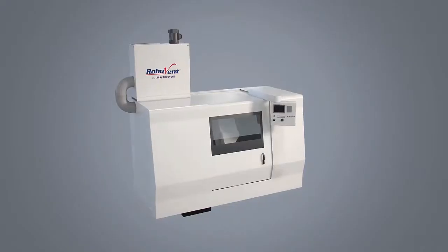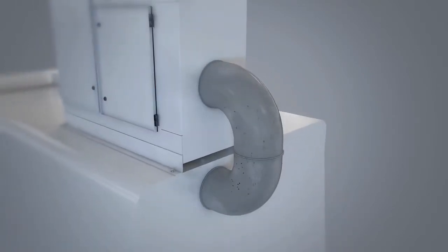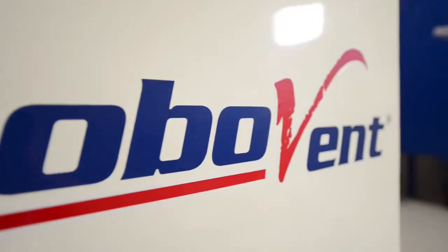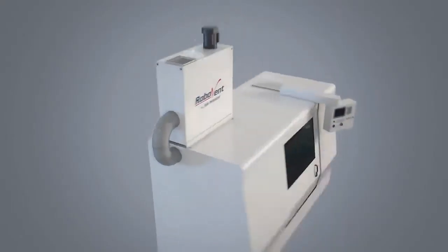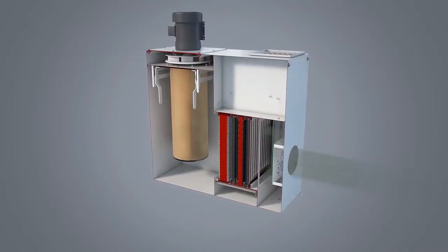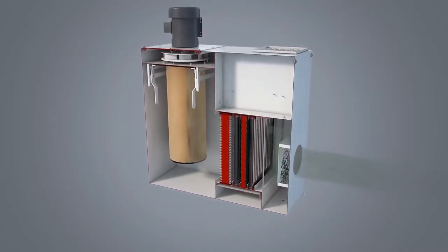Mist and smoke are drawn up into the Clarion unit, where the coolant is captured and recirculated back into the machining center. The very fine mist, along with smoke, now meet up with a five-stage filtration process.